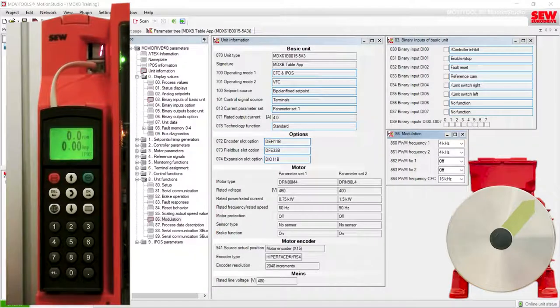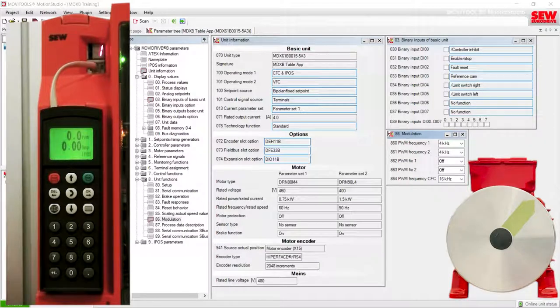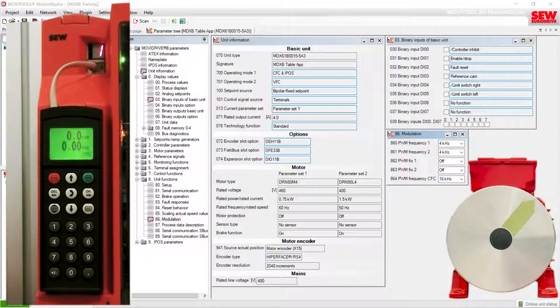Looking at Motion Studio, we can see parameter 700 is now set to CFC and IPOS, the PWM frequency for CFC is back to 16 kHz, and our motor information still shows DRN80M4. This concludes the features of the keypad I wanted to demonstrate in this lab. The keypad is quite capable when you don't have access to Motion Studio software. It's easier to navigate MOVIDRIVE parameters using the keypad if you know the specific parameter number, but if you don't, you can use the arrow buttons to search or download the MOVIDRIVE system manual which has the full list of parameters and their descriptions. In the next lab activity we will switch back to using Motion Studio software and change our table positioning application module to a different application that uses data over the ethernet fieldbus to control the MOVIDRIVE instead of the digital inputs. Thank you for your attention, take care, and have a good day.